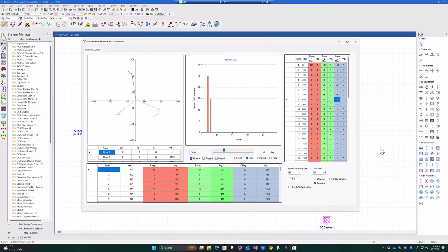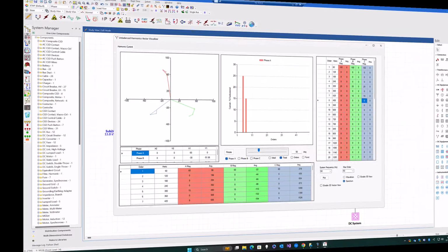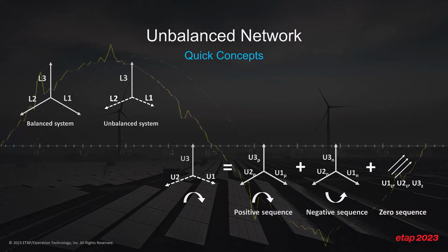So speaking of unbalance, let's look into the unbalanced network concepts really quick. Distribution systems are also quite often unbalanced in nature. And when I say distribution systems, it's not just utility distributions, it's electric distribution systems in general. Disturbances or short circuits are usually amongst many reasons that result in an unbalanced system, but an unbalanced system is more often caused by various factors that include unbalanced loads, unequal mutual coupling between the transmission lines, and unbalance also occurs in three-phase power systems when single-phase loads such as lighting, office equipment, etc., don't draw the same amount of current on each phase, resulting in greater stress on the neutral conductor.